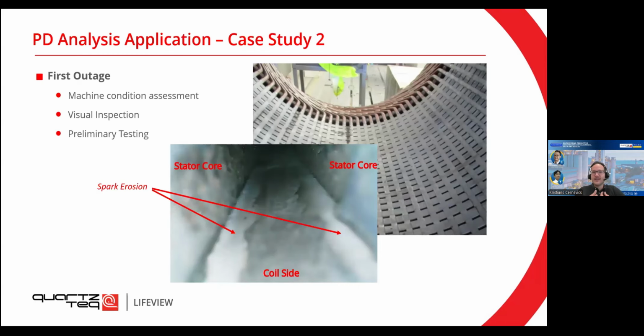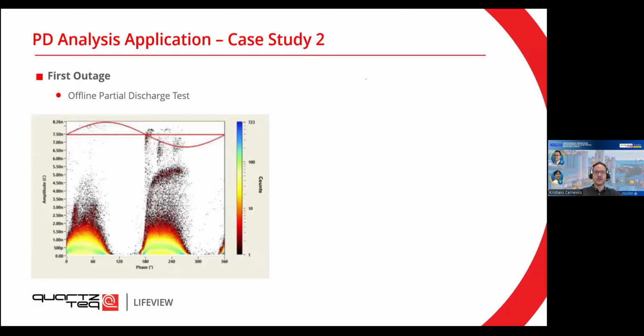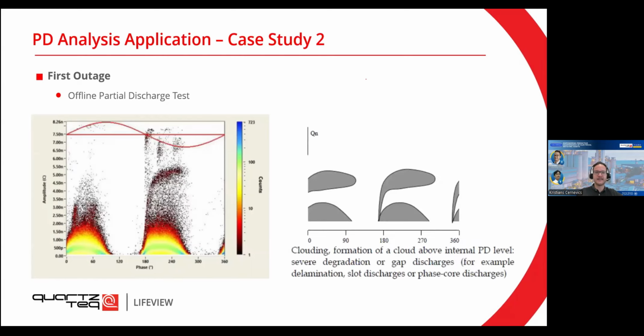So in our opinion, this is already a bit too late. Once you do the outage and you see that the damage is so high, condition monitoring could have prevented this. They did an offline partial discharge test. They saw quite high values and also this kind of indicative cloud forming above the internal PD level. So this means that there is some kind of gap discharges happening. So something more serious than just some small internal discharges.